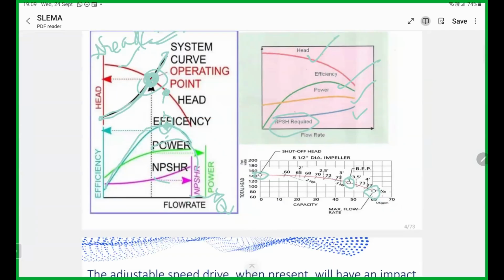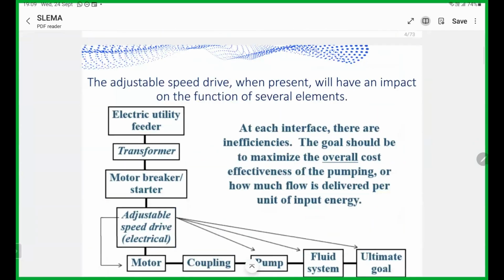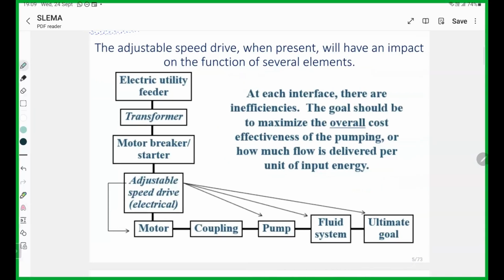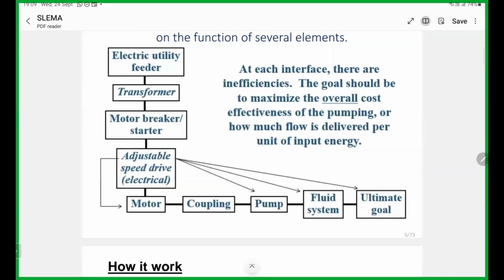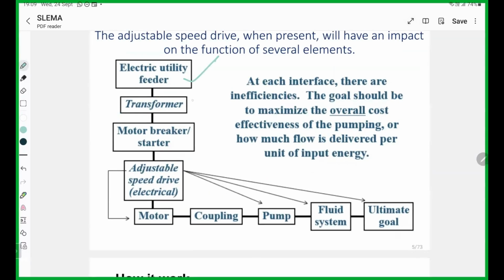Then if you come to this one, the system approach is very important when you think about centrifugal pump energy conservation. Generally we have the electricity utility feeder, the utility supply. Then we have the transformer, motor breaker, starter panel, and starter. Sometimes we have a VFD. Then it comes to the motor, then coupling, then the pump, then the fluid system, and ultimately we deliver the required pressure and required flow. At each and every step we have inefficiencies, right?